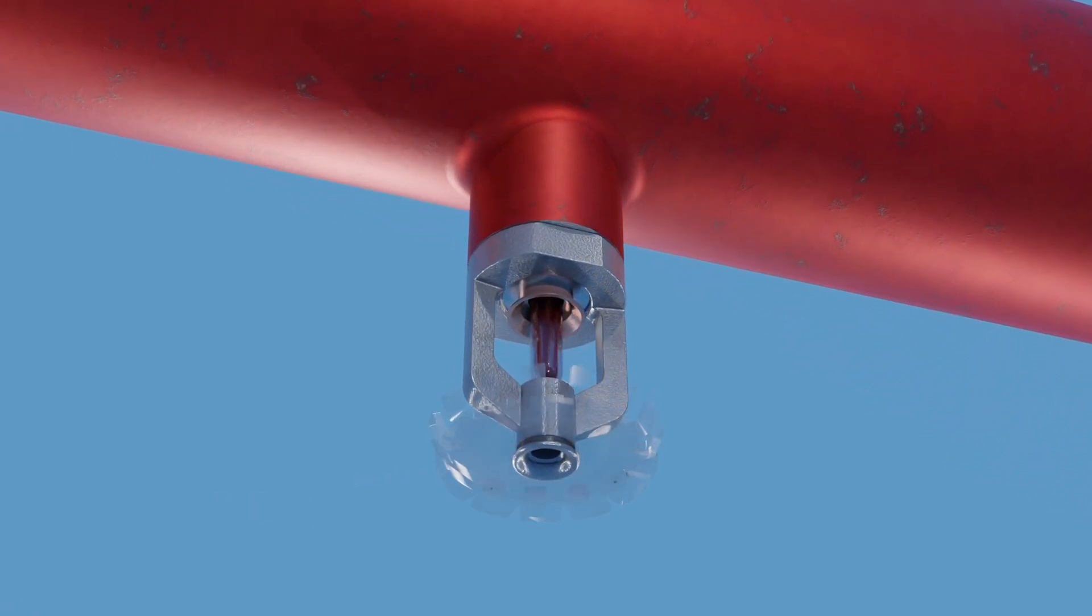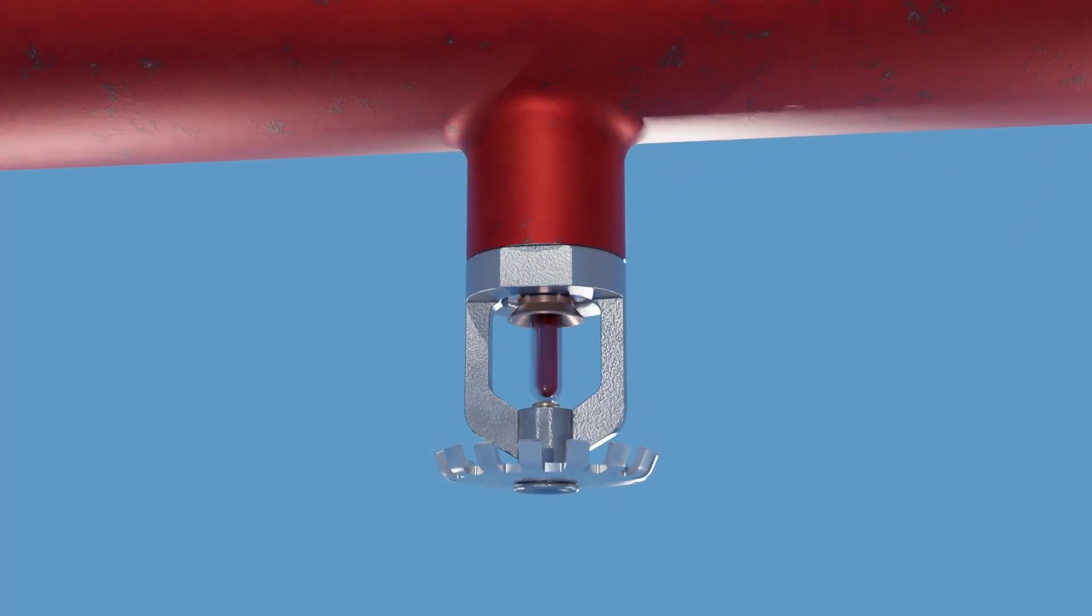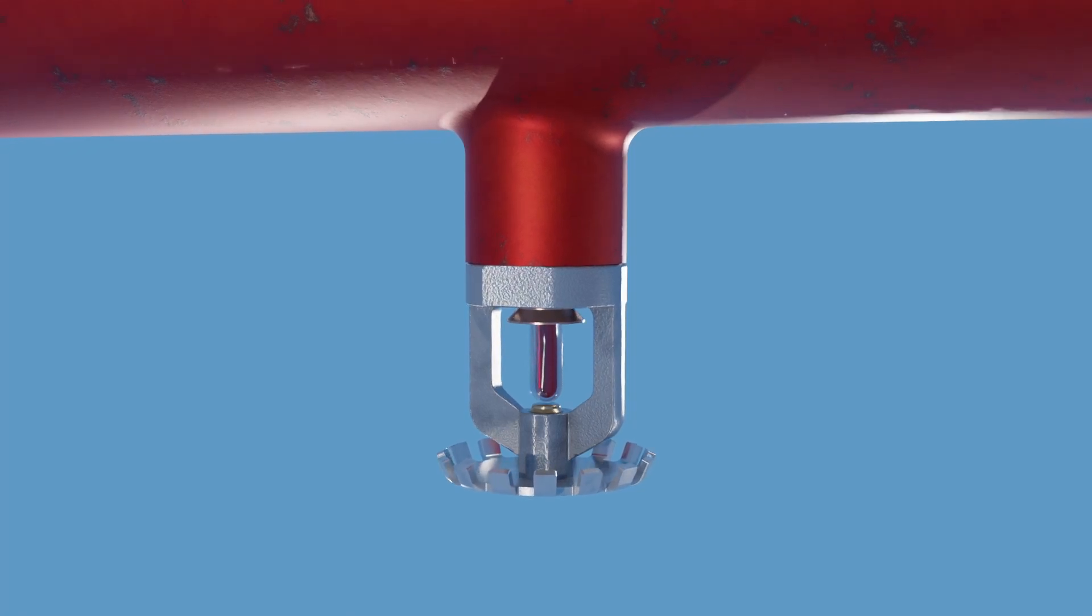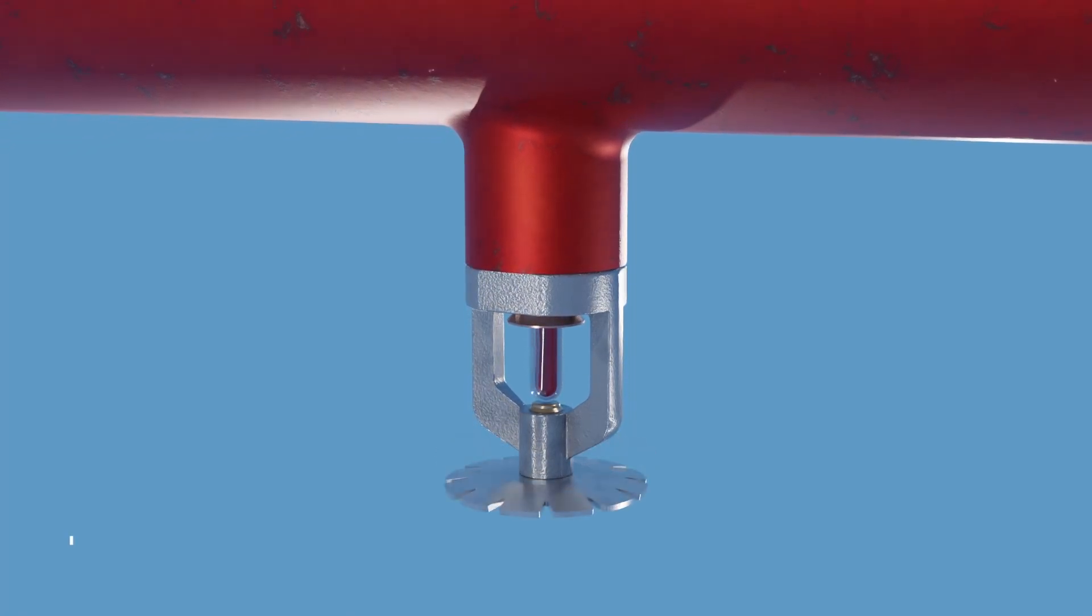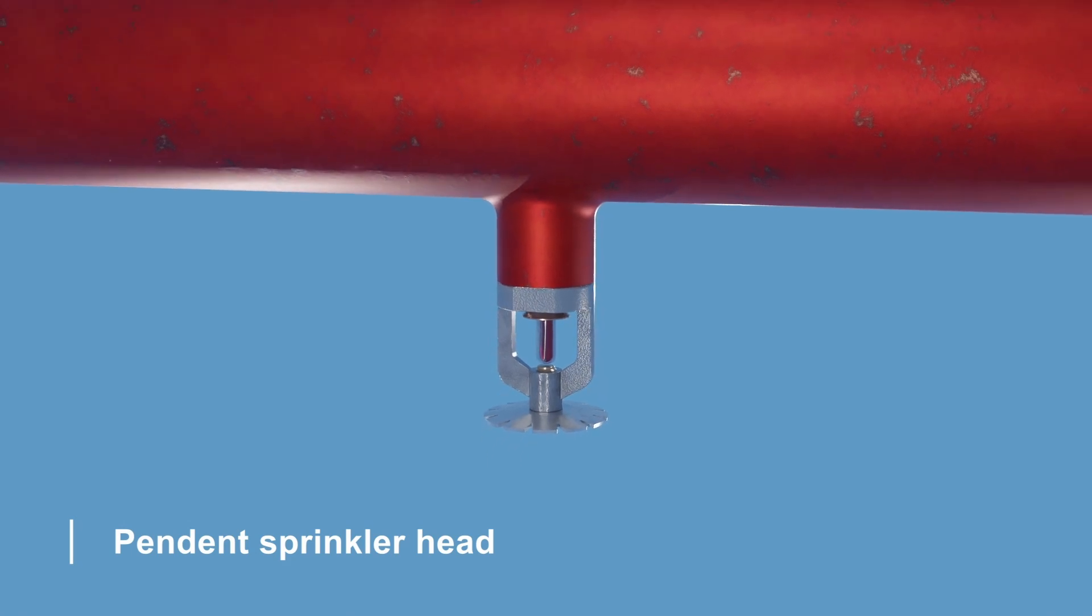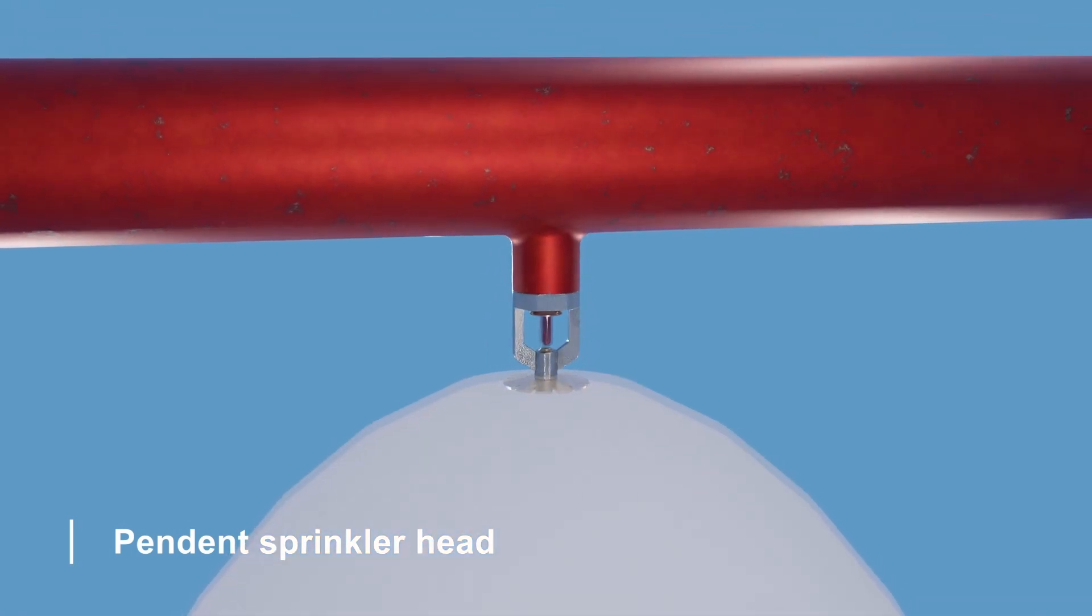There are several sprinkler head types designed for specific applications, each using a different deflector. Let's explore the two most common types available. The pendant sprinkler head is the most common type. It is installed hanging down from the ceiling pipes and directs water downward in a conical spray pattern using a convex deflector.